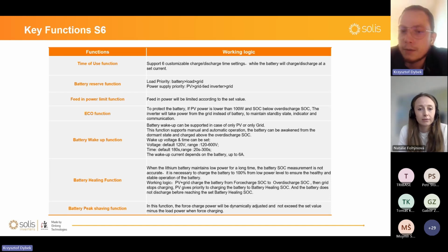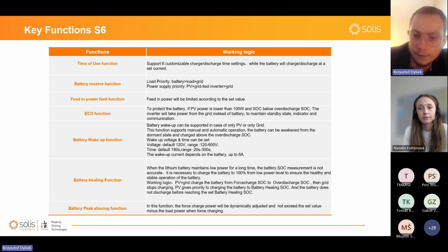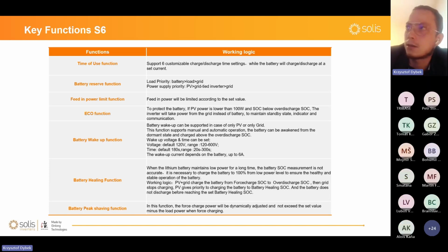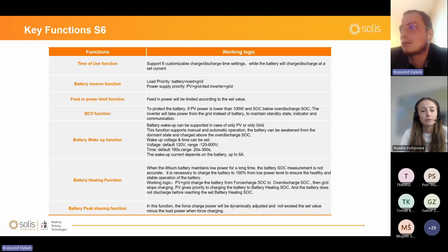This is to not drain the battery that much. If your PV is too low to keep the inverter in operation, it will take power from the grid for its own self-use to avoid draining the battery too much. Battery wake-up function. It sends current to the battery to wake it up. It is useful if you suspect that the BMS is not responding. This is like a shot of energy to the battery. If you really suspect that your BMS is maybe broken, or you are not sure if your battery is discharged totally, it is better to have this option, especially with some battery manufacturers.